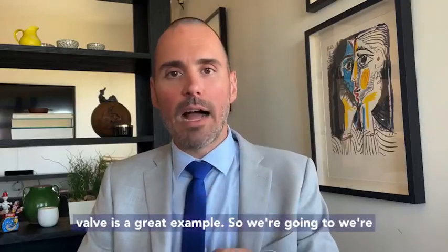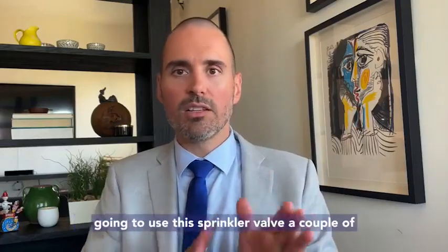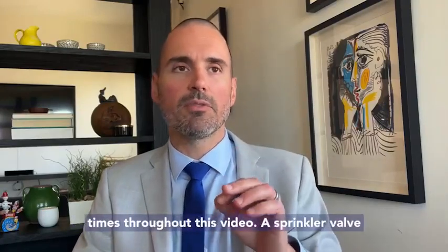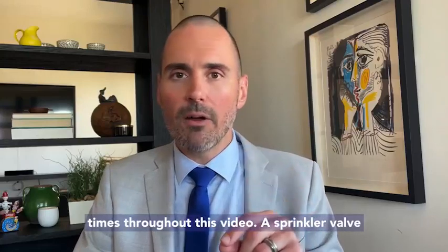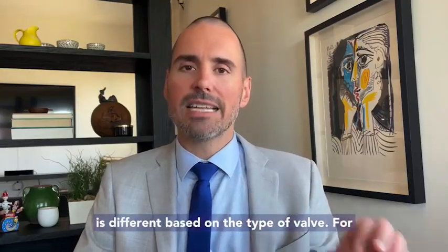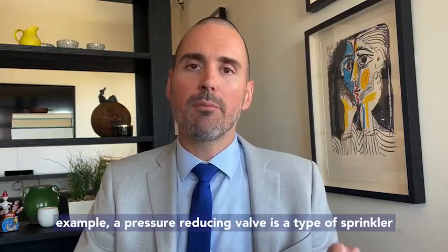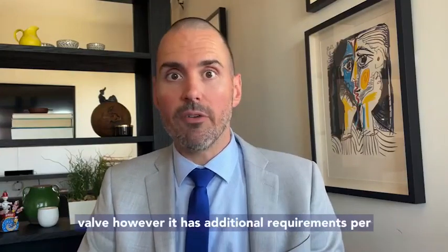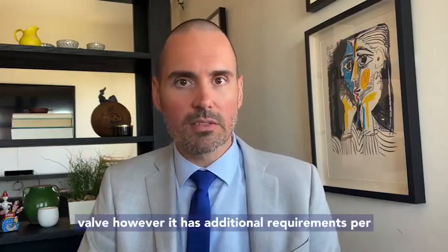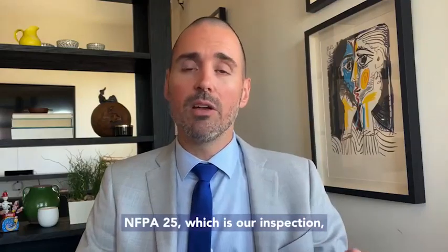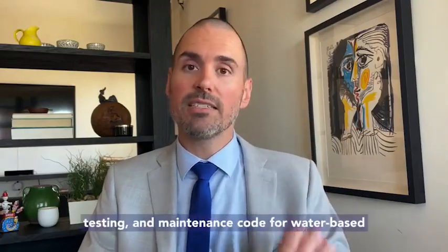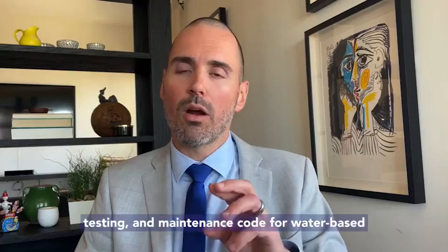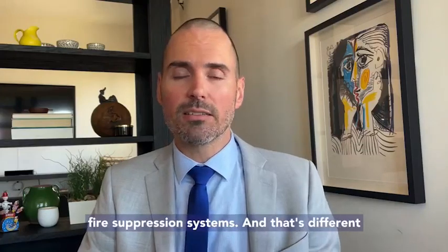Well, sprinkler valve is a great example. So we're gonna use this sprinkler valve a couple of times throughout this video. A sprinkler valve is different based on the type of valve. For example, a pressure reducing valve is a sprinkler valve. However, it has additional requirements per NFPA 25, which is our inspection, testing, and maintenance code for water-based fire suppression systems.